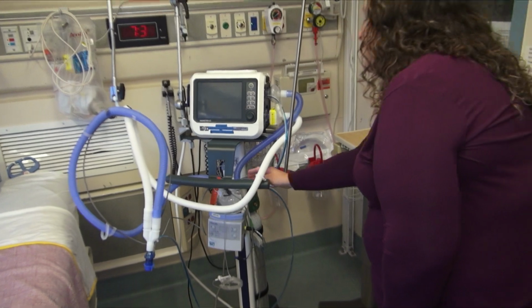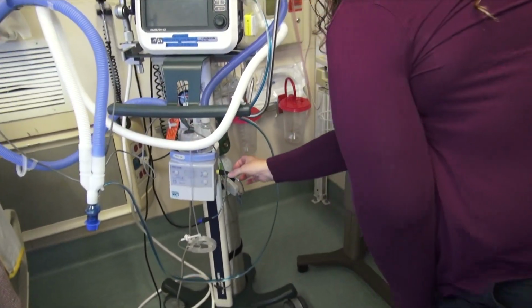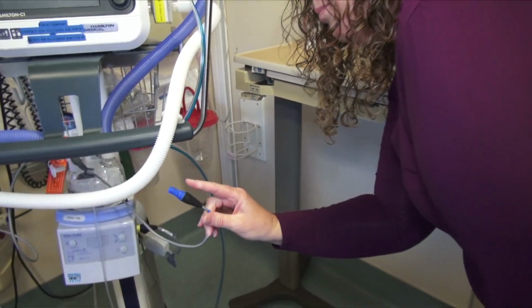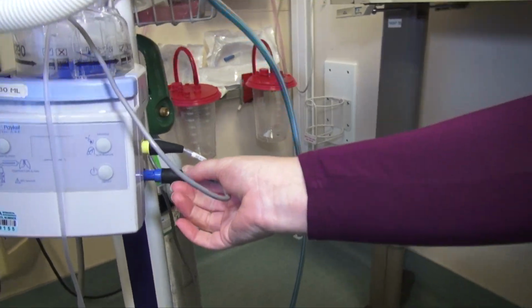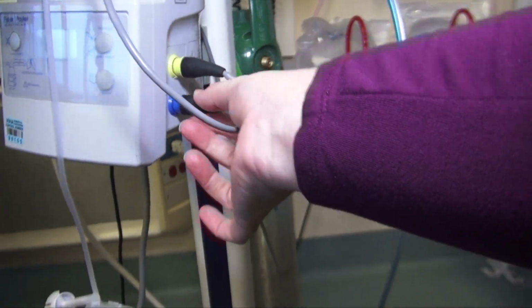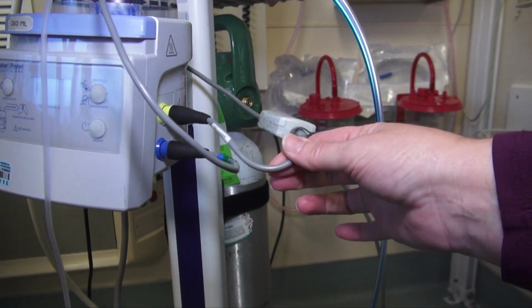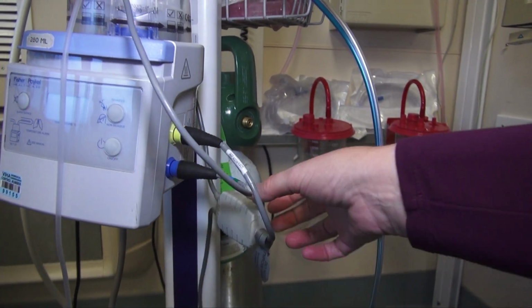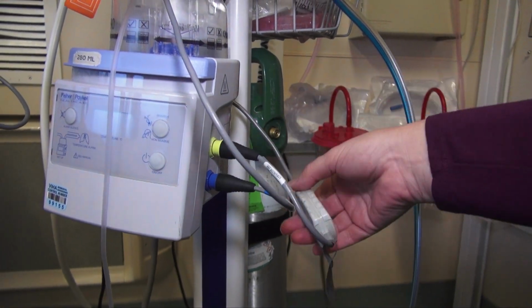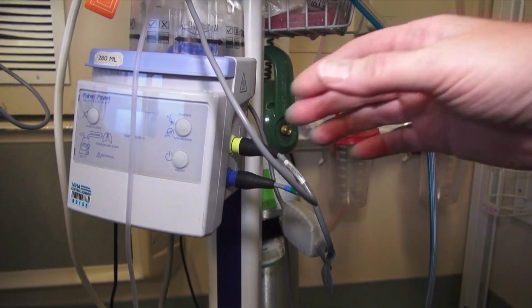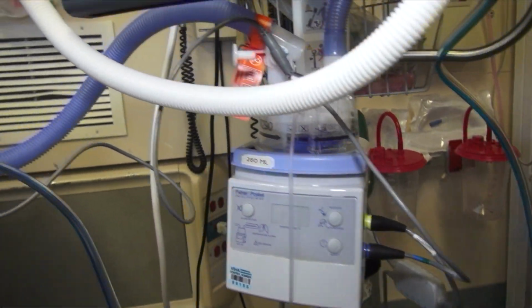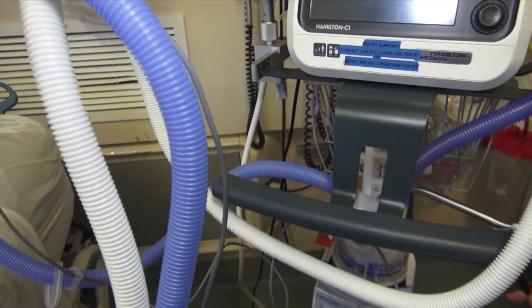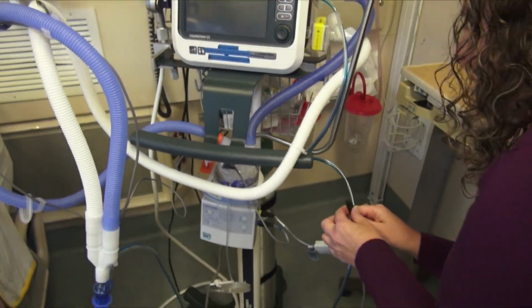Last things that you need to connect is the humidifier. You have a blue plug, and there is a blue plug here. We're just going to slip that in. This is the module that makes the heated humidifier work. It stays with the unit when you're cleaning it. The only one that goes to MDR is the actual humidifier probe that is inserted into the inspiratory limb.